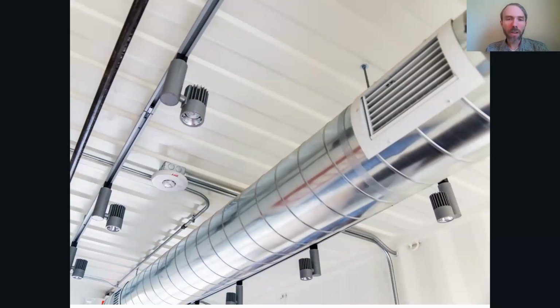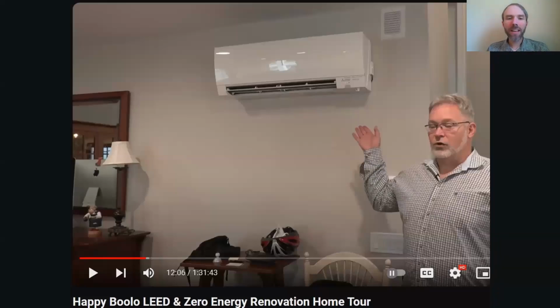So if you have multifamily projects that are like that, or you're tearing out the drywall, you can do this, and that will also help reduce any expenses if your rater doesn't carry around duct leakage testing equipment or doesn't charge you for the fees for that, or you're in another country where a lot of times that's harder to access. If you cannot get the ductwork fixed within your budget, adding a ductless or ducted mini split may be the solution, which then avoids the need for the ducts and duct leakage testing.